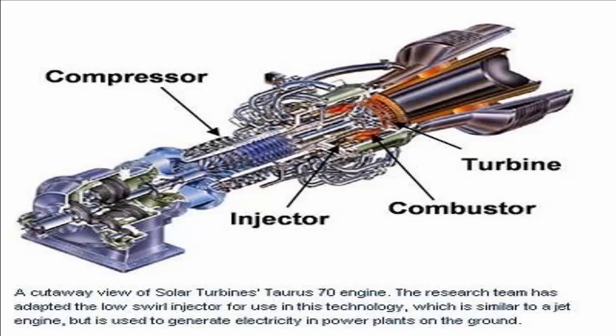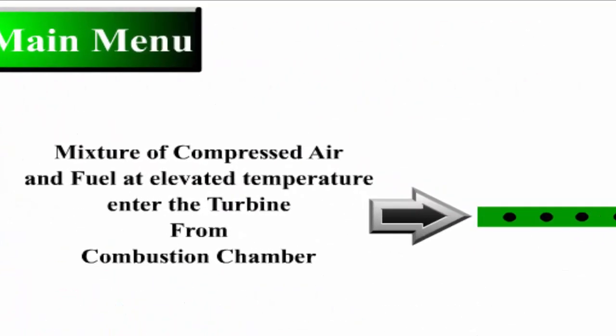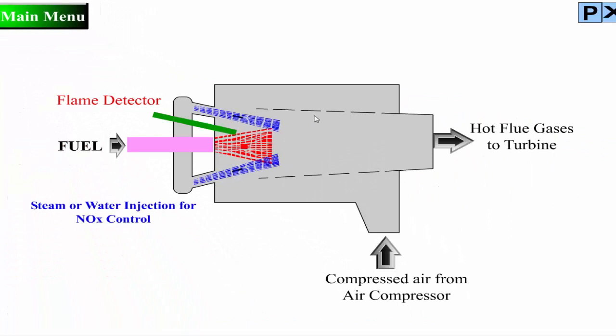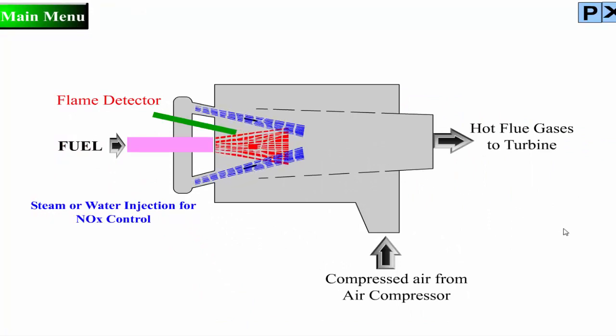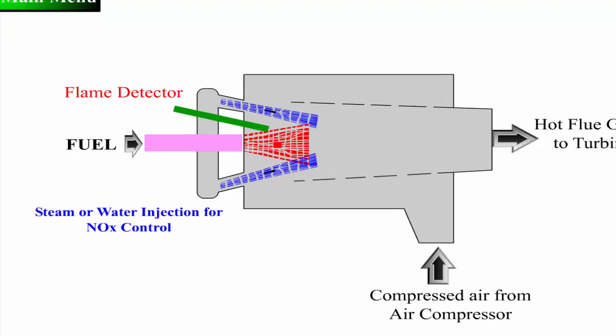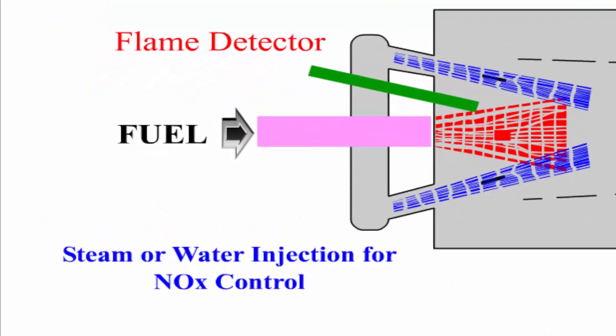Aeroderivative engines are derived from jet engines, as the name implies, and operate at very high compression ratios, typically in excess of 30. Aeroderivative engines tend to be very compact and are useful where smaller power outputs are needed. As large frame turbines have higher power outputs, they can produce larger amounts of emissions and must be designed to achieve low emissions of pollutants, such as NOx.